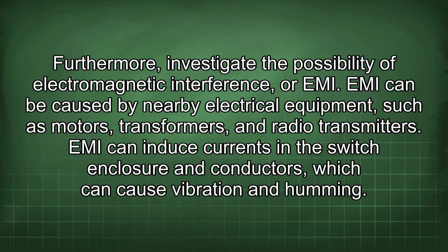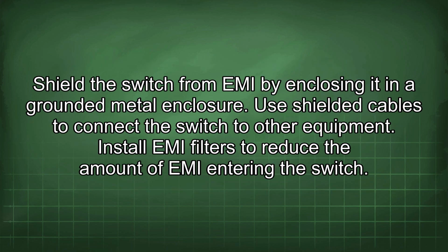Furthermore, investigate the possibility of electromagnetic interference, or EMI. EMI can be caused by nearby electrical equipment such as motors, transformers, and radio transmitters. EMI can induce currents in the switch enclosure and conductors, which can cause vibration and humming. Shield the switch from EMI by enclosing it in a grounded metal enclosure. Use shielded cables to connect the switch to other equipment. Install EMI filters to reduce the amount of EMI entering the switch.